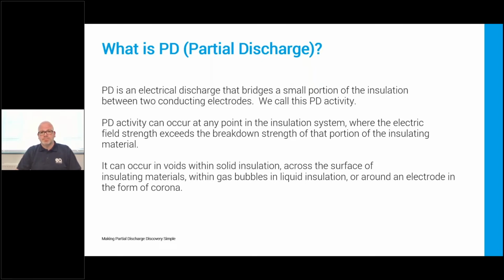So it can happen in voids within solid insulation. It can track across the surface of insulation. It can occur within gas bubbles in liquid insulation, so oil-filled transformers, for example. Or it can form around an electrode in the form of corona.